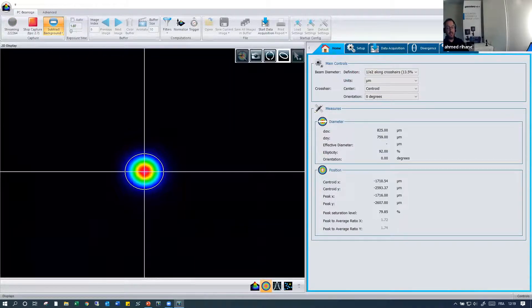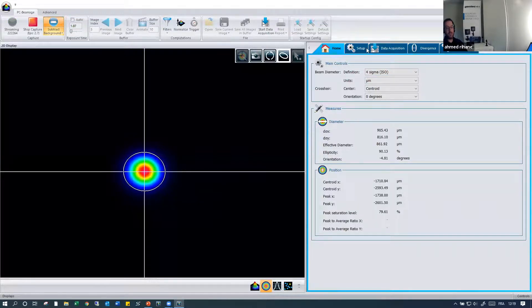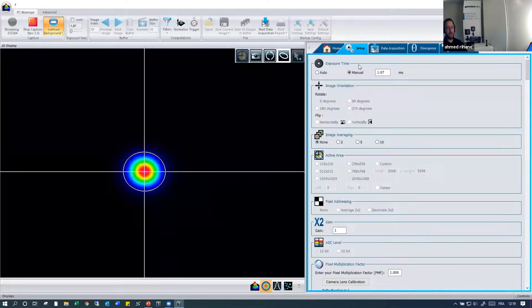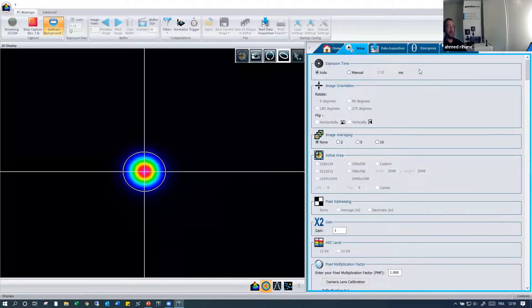Now let's look at the inputs we talked about earlier. Here you can see the beam definition options — it is set to four-sigma by default. You have the exposure time, which you can set to automatic or manual. You have image averaging, active area, and other options you can change depending on each situation to optimize your beam profile measurement.